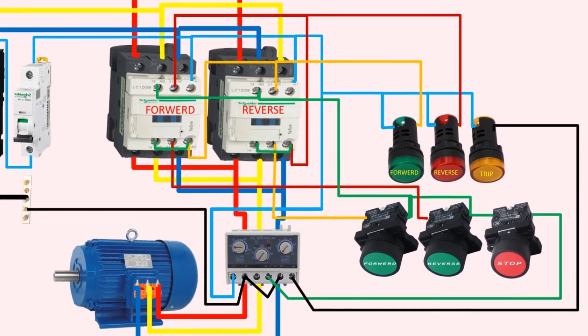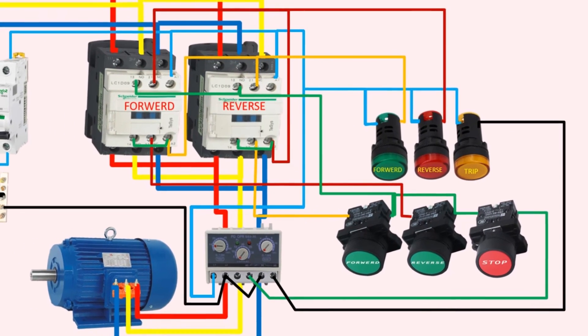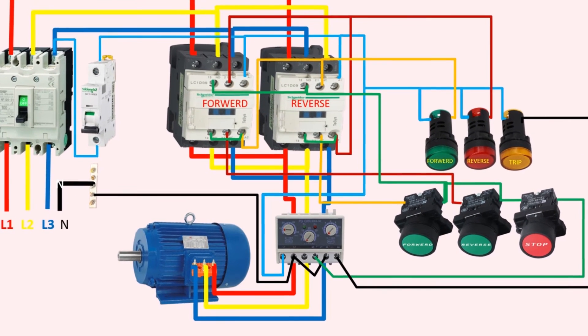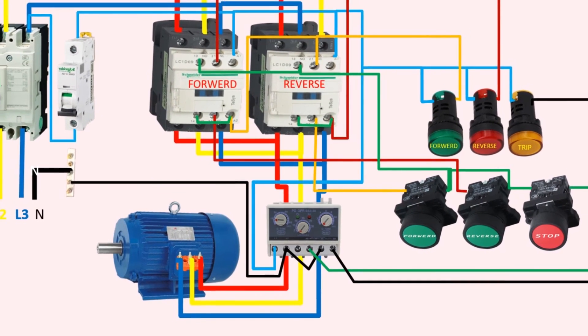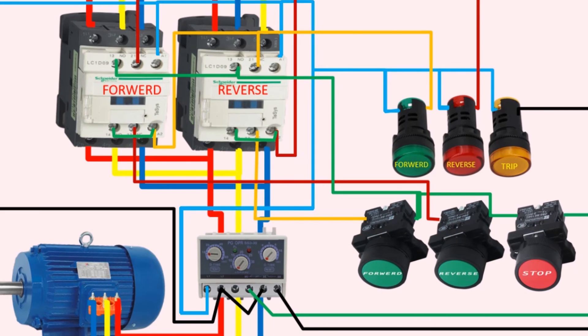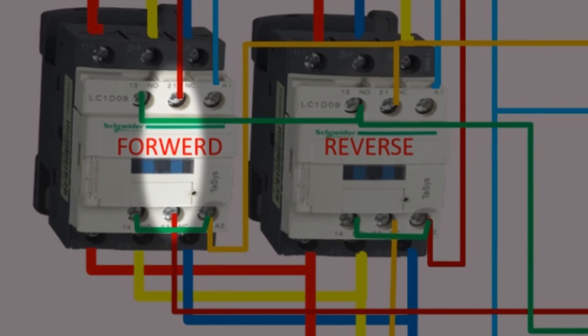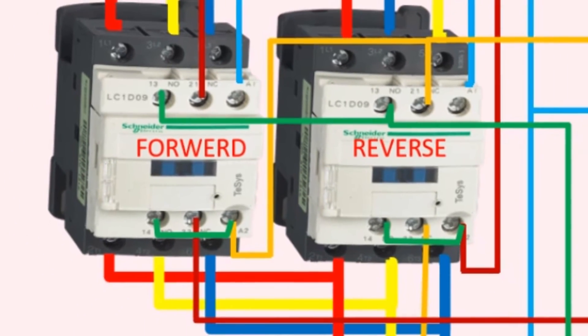When we want to run the motor in the forward direction, we press the forward push button, causing the forward contactor to operate and its normally open contact to close. This allows the current to flow to the motor, causing it to run in the forward direction. However, if we were to press the reverse push button while the motor is already running in the forward direction, it will not work because the dark red wire passes through the normally closed contacts of the forward contactor, which are already open. This is due to the electrical interlock between the forward and reverse contactors, which prevents both contactors from operating simultaneously.